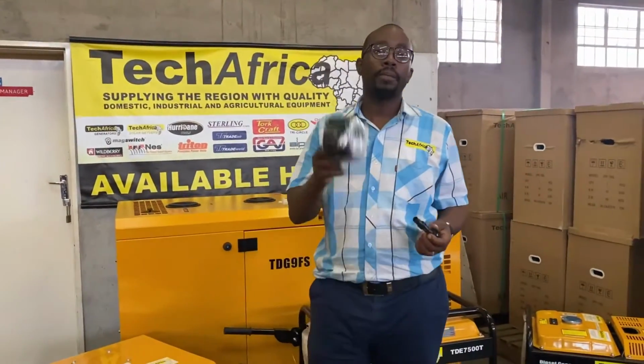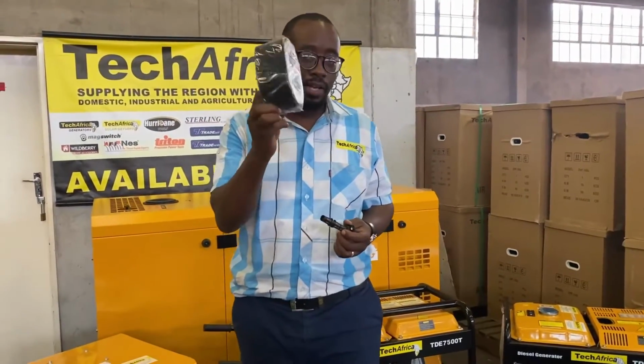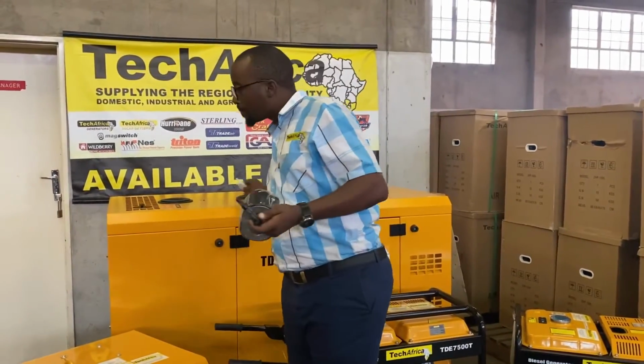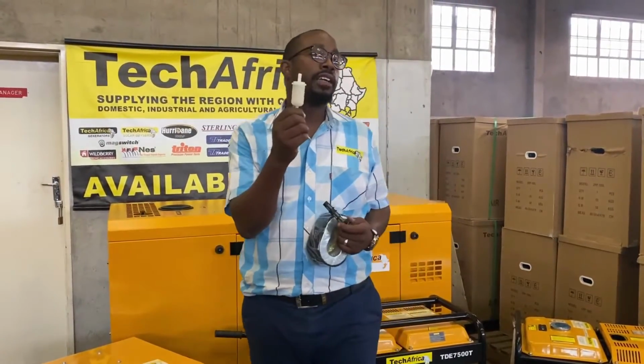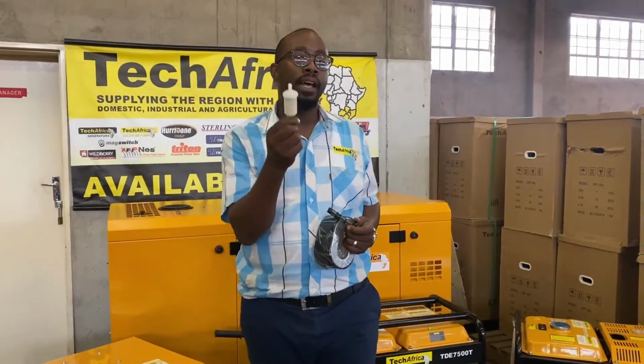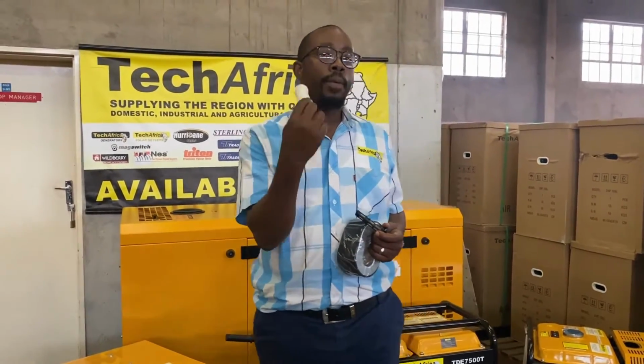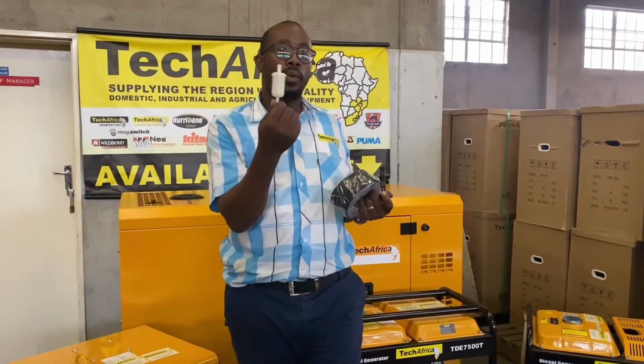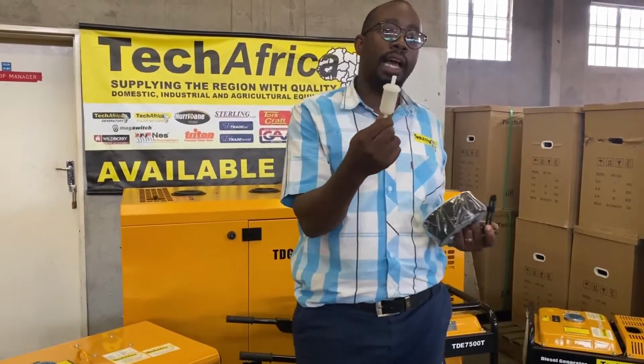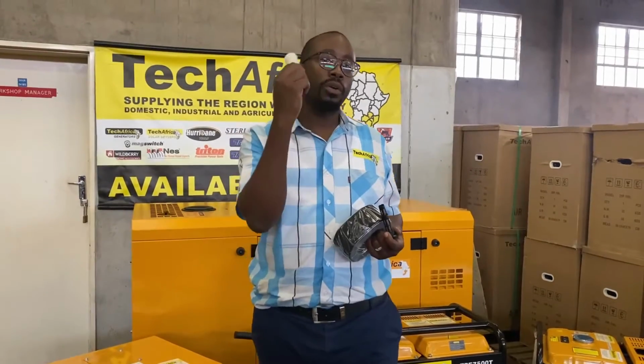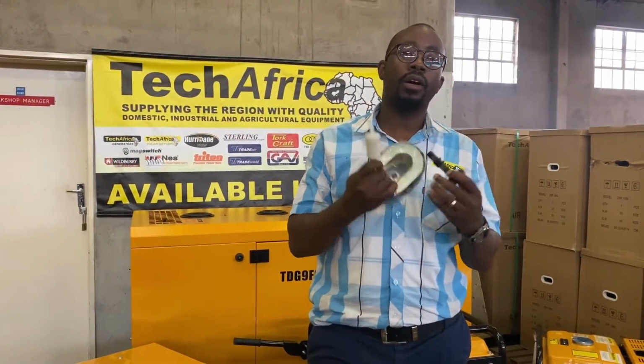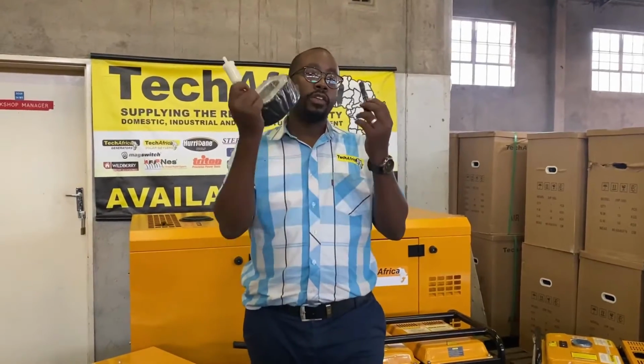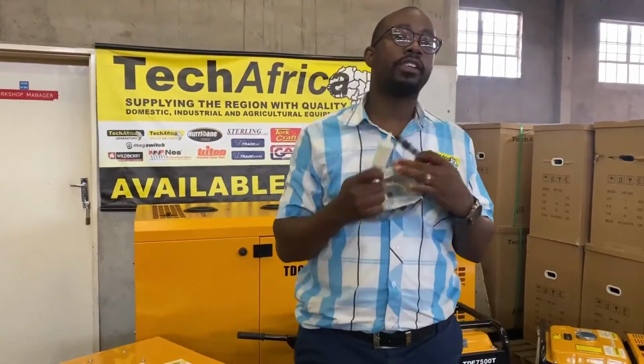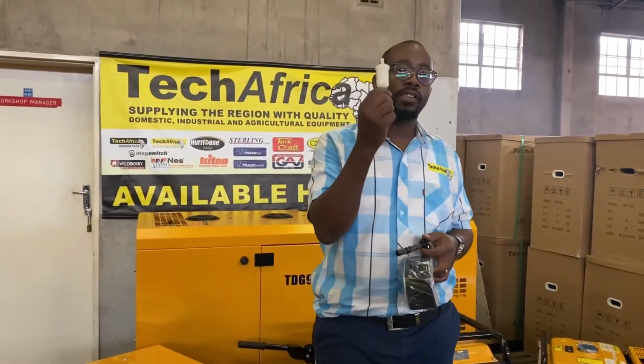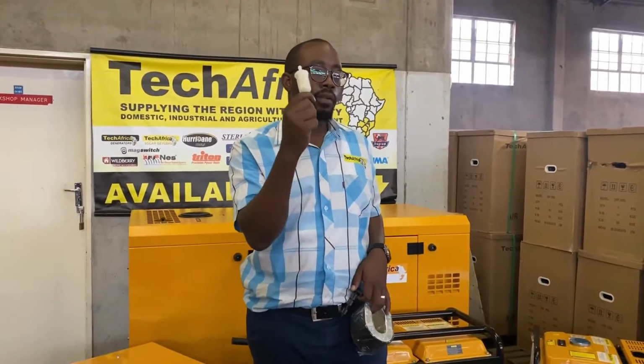When your generator reaches 75 hours, we recommend changing the air filter—this is the air filter, and this is the oil filter. Occasionally you might need to change the fuel filter, but we don't recommend doing that regularly, maybe every 100 to 150 hours. So generally every 75 hours change your oil filter and air filter, but every 100 hours make sure you change your fuel filter.